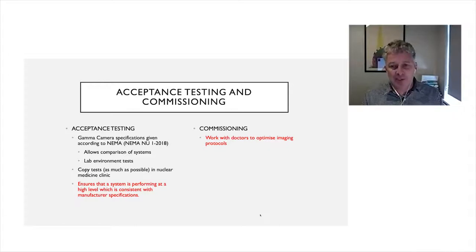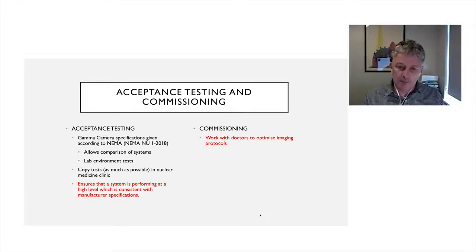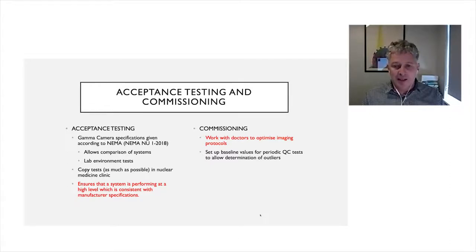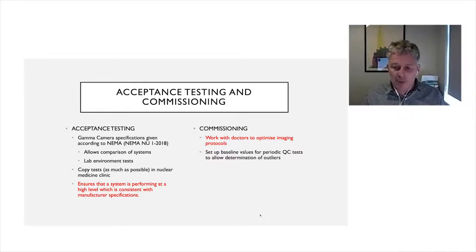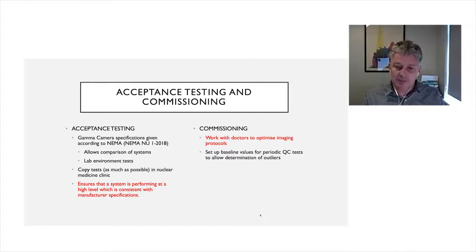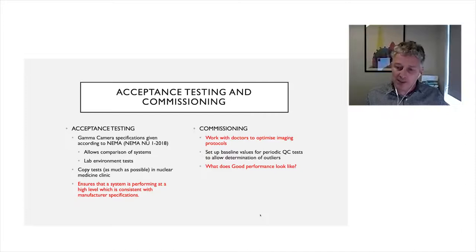Commissioning really has two steps. The main one is working with doctors to optimize imaging protocols and make sure all scanning protocols produce the images needed for clinical reporting. The second element is setting baseline values. Immediately after acceptance testing, the camera is at its highest performance level — a perfect time to run repeat periodic QC tests and establish a range of what the gamma camera is capable of. Then during routine periodic quality control, we can check whether daily or monthly values fall outside these baseline values.